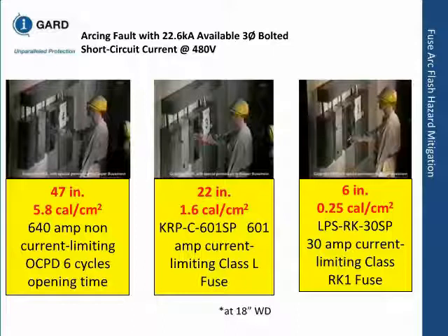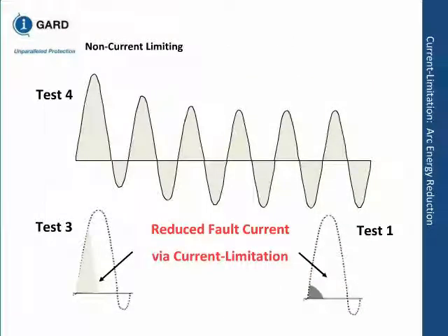This is the same as what you see in the test. In test 4, you can see the energy. It all started from here. It took all the time, 6 cycles, to interrupt. And you can see it keeps on going down, as opposed to test 3. Energy has been substantially reduced. So if you highlight the area between these curves, that will give you the energy. Now at the 30 amp fuse, you can see how quickly it cleared. So wherever you can use smaller fuses, that's where you should use them, as opposed to using the biggest fuse you can put. You should check your system and use current limiting fuses to lower the level.